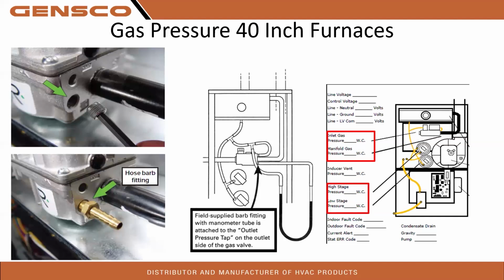So let's get into the 40-inch furnaces. You have a barb fitting you're going to have to get into. On the newer 40-inch, they have a boss, right? A pressure inlet boss. They are sealed combustion. On the old 40s, they have a door over the burner, and you have to reference the burner, or you have to take the door off the burner to get a true number for gas pressure, right? So if it's a barb style, you're going to have to get into it. If it's an inlet boss, you're going to have to unscrew it and stick your hose over the top.